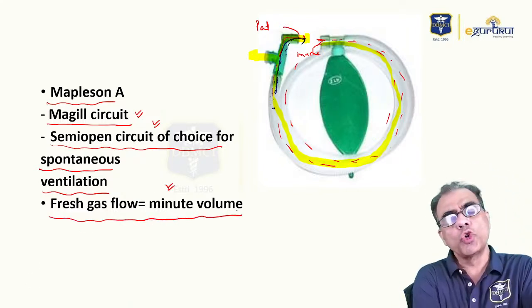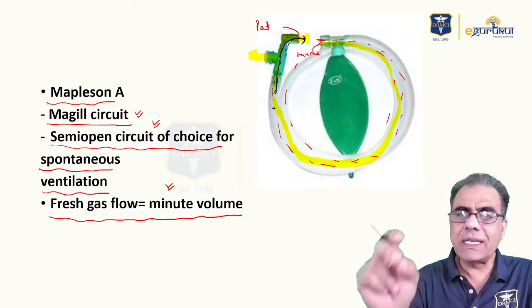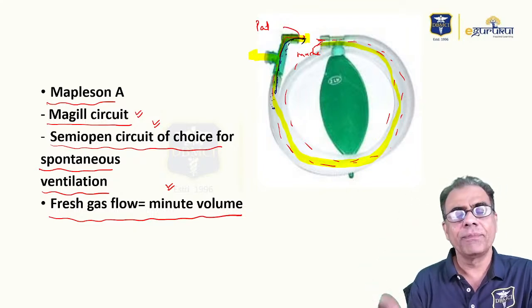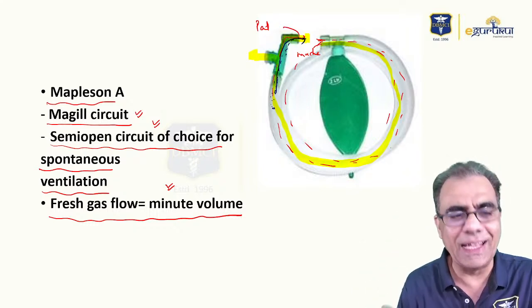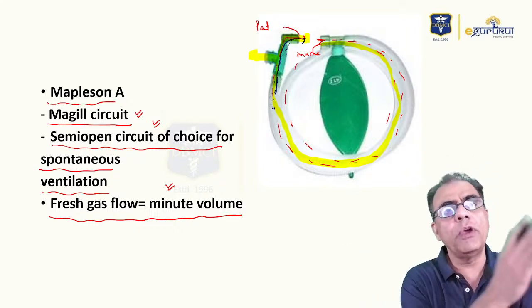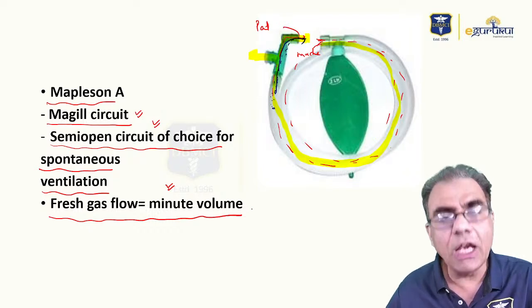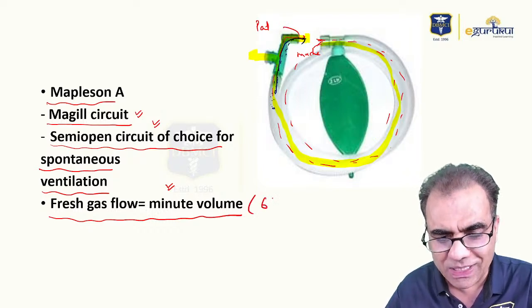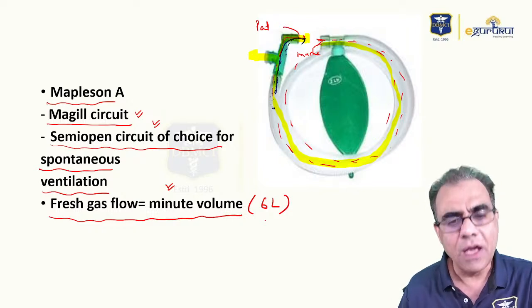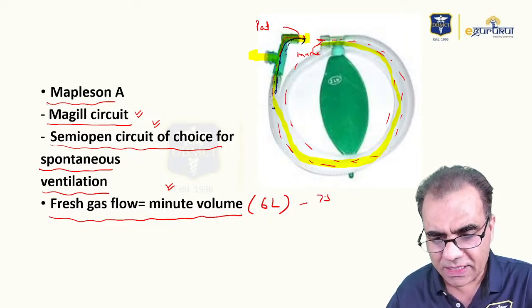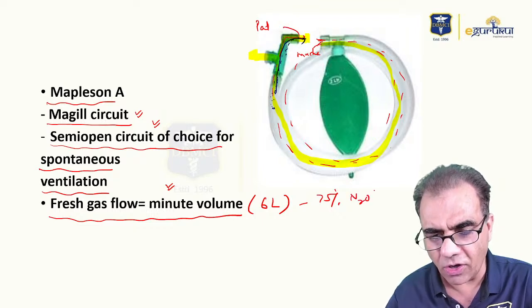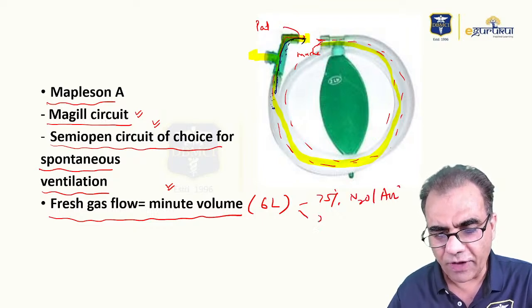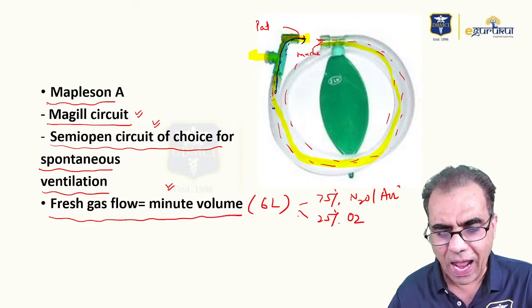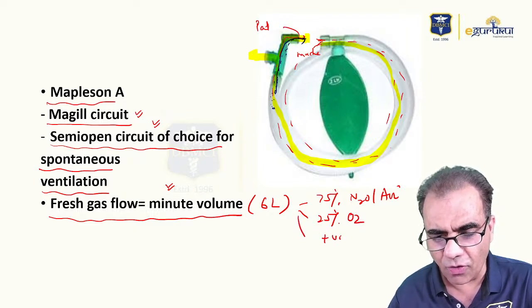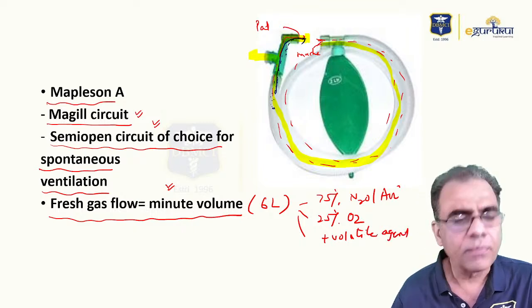Fresh gas flow should be equal to the minute volume. Means if you are using Magill circuit and the patient is on spontaneous ventilation, then fresh gas flow coming from the anesthesia machine should be equal to minute volume, or I can say around 6 liter for an adult patient. Out of this 6 liter, 75% should be nitrous oxide or air, 25% should be oxygen, and plus it contains one of the volatile agents. So this is the combination we give to the patient.